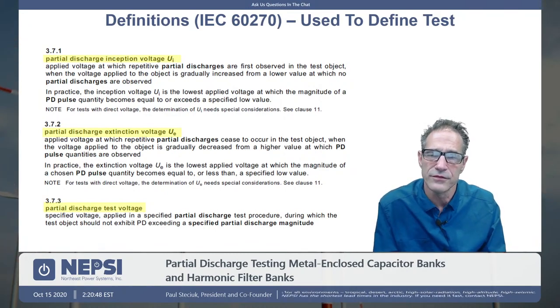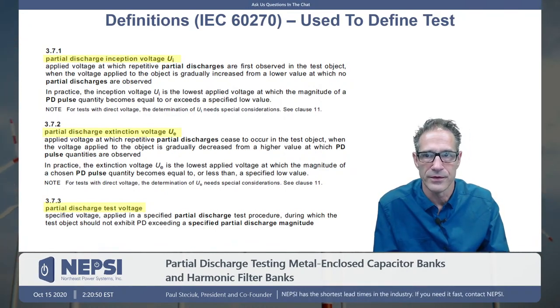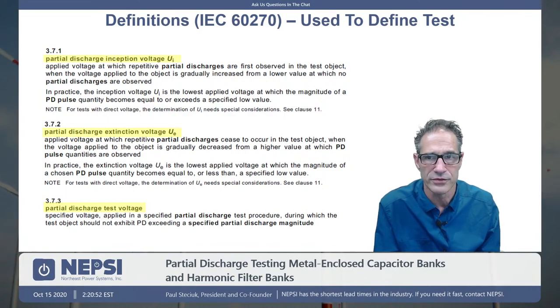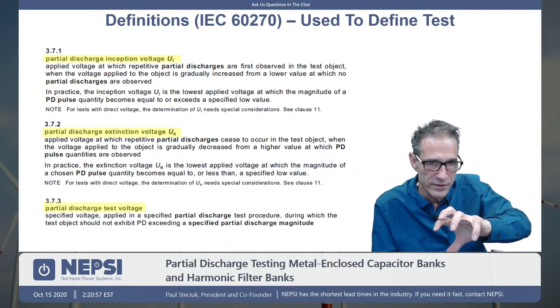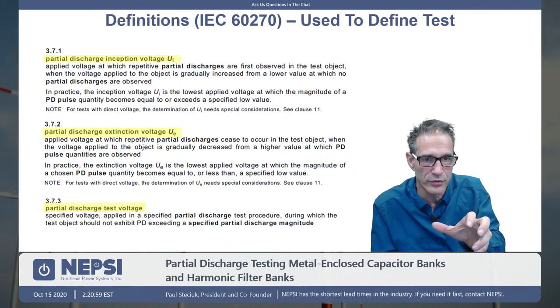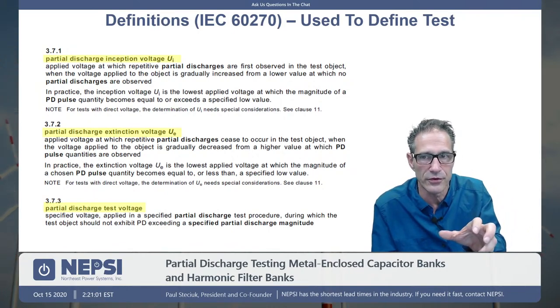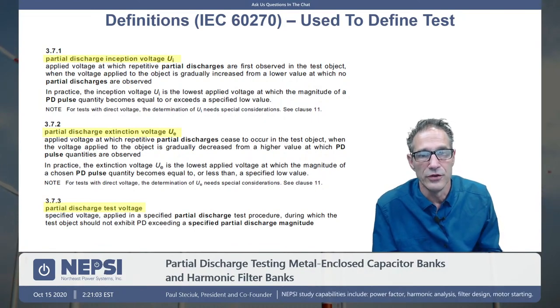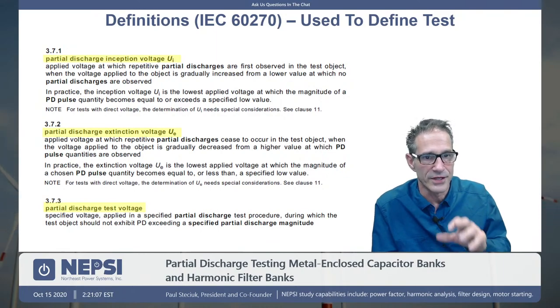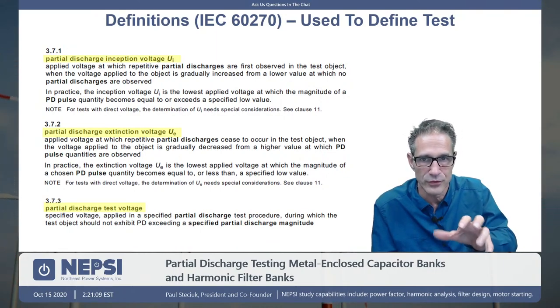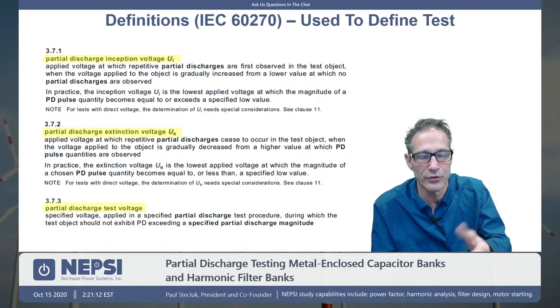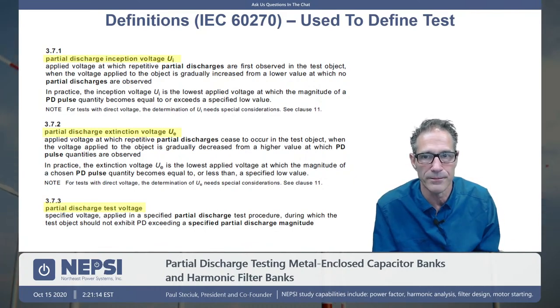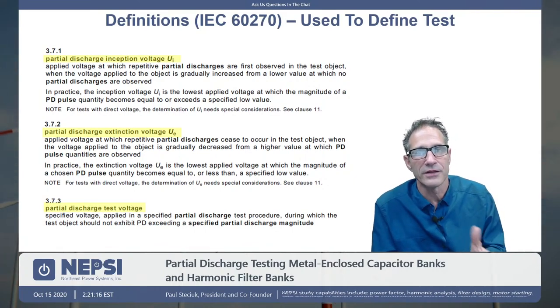So we have the inception voltage. That's where corona begins. It's where you have this partial discharge occurring. So as you do your high pot test and you start to raise your voltage, you'll get to a point where partial discharge will start to occur. And you can see this on the meter, and that's called the inception voltage. That's where corona begins, or partial discharge begins. And I keep using the word corona, but technically I should be using the word partial discharge. You get the extinction voltage.